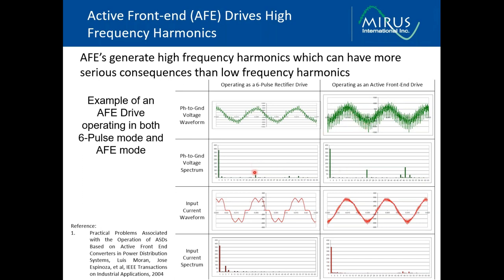You can see it in the harmonic spectrum here. There are high frequency currents or voltages introduced here, at much higher levels when operated as an AFE drive. The input current of the six pulse drive shows very typical double humped waveforms, with fifth and seventh being the predominant harmonics. This will typically not meet the standards, because of the fifth and seventh harmonics.